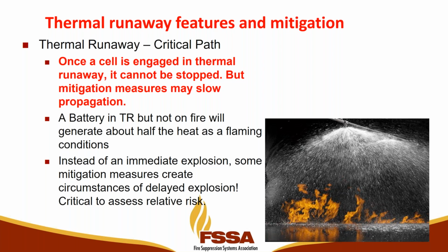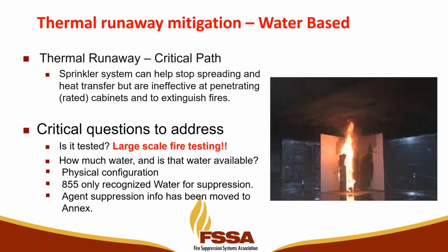Make sure you understand that risk when you're putting these systems in. Are there unintended consequences? Sprinkler systems may help stop the spreading, but they traditionally are not very effective at penetrating the cabinet and extinguishing the fires. They're very good at heat transfer. So when you look at a 0.3 density, does that really work? Probably not. FM has done some large-scale testing. But then how do you get in and use water as a viable backup? How much water is available?